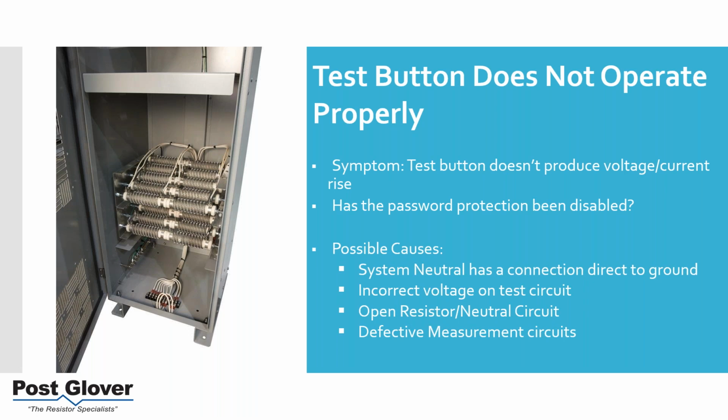One possibility for sure is you have a solid ground. The next thing I would do after that is I would take a multimeter, actually measure an XO to ground resistance measurement, and see if that's solid grounded. I mean, it's as simple as that.